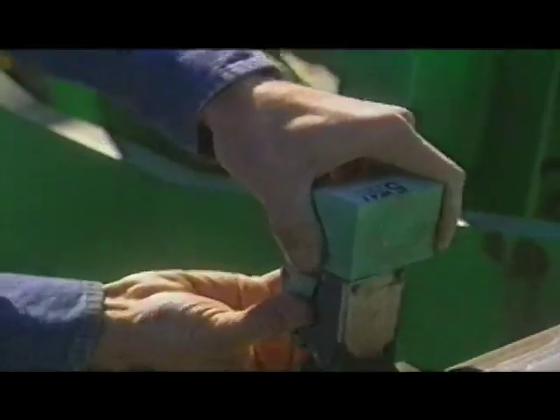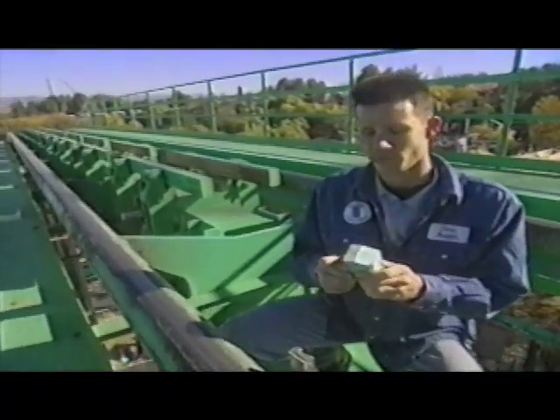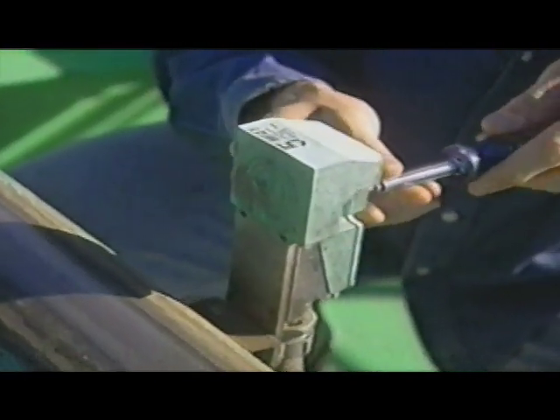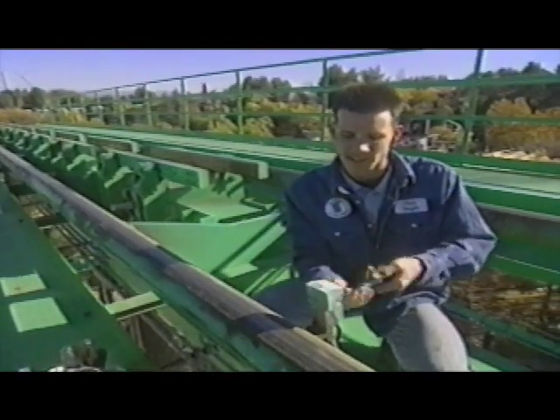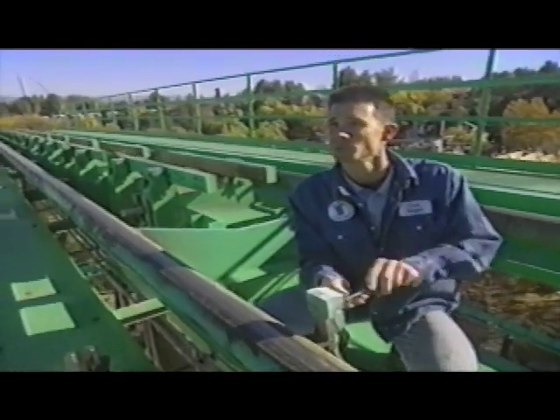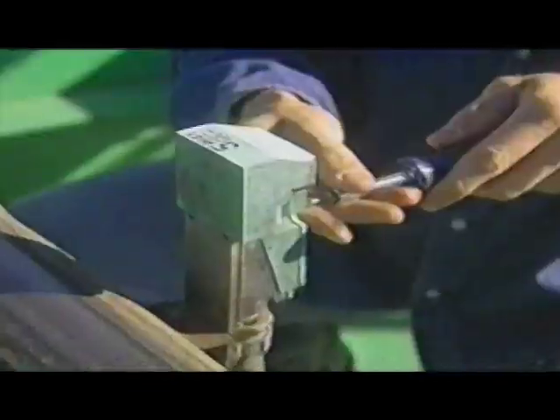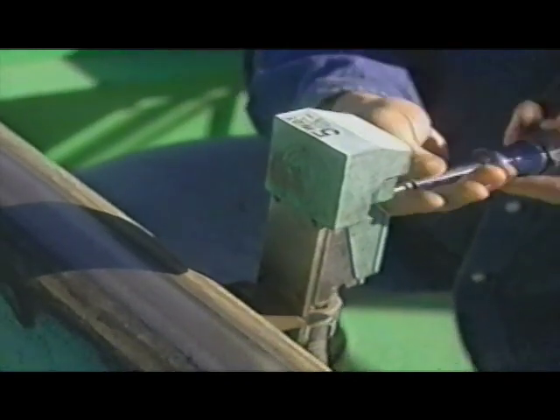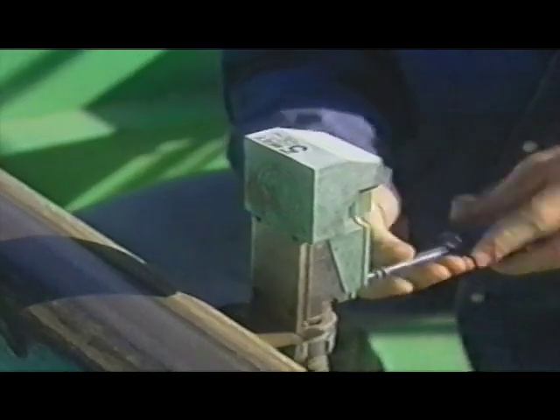This right here is one of the sensors we have mounted on the track here at Riddler's Revenge, similar to most all rides. The way the sensor works is that it's mounted on the track just like so. And what happens is when the train goes by, the wheel of the train, it senses that in close proximity just like that, and then it sends a signal back to the computer, the PLC. And that's how we know where the trains are at all times. Right now I'm just checking for loose connections and whatnot. Very typical, one of the things we need to do on a maintenance level.